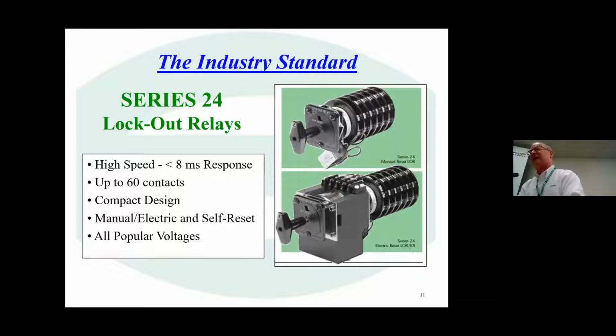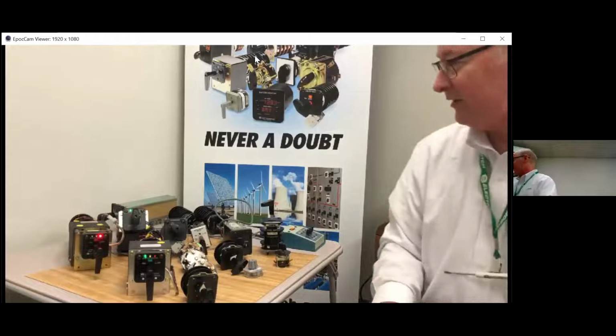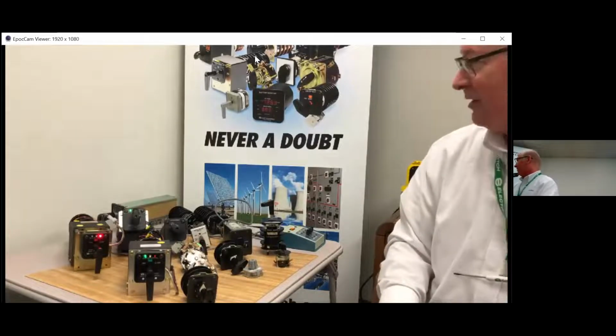We started out at 10 decks maximum, and over the years we've been able to increase it up to 15 decks, which would give us the 60 contacts. In that particular design, we have a compact design, a manual electric operated design, and a self-reset design in all of the popular voltages. So with that, let me do a little hands-on demonstration again and show you the lockout relay and how it operates, as well as some of the other devices that I'm talking about electrically.